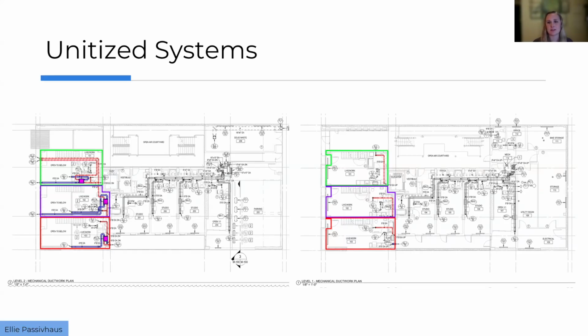The pros of this is there's autonomy in having just 1 system per unit. It's very simple to balance in that there are fewer grills and intakes and exhausts. So by changing one airflow, it's not going to too drastically affect the other. I've just personally found it to be a bit easier to balance smaller units.